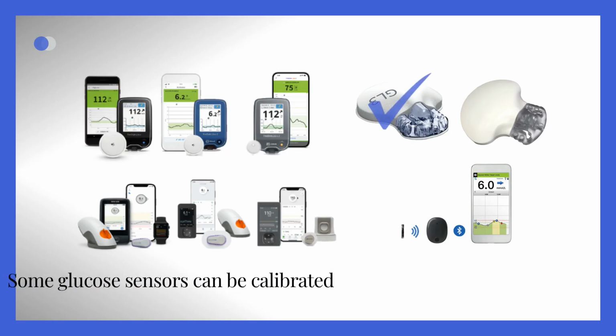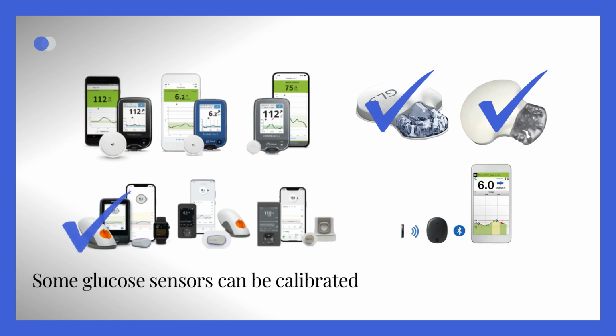In case your sensor continually demonstrates a divergence from finger prick readings under stable and target range glucose conditions, consider calibrating it if it supports this feature, or replacing it with a new sensor. When contacted, most companies will typically provide a replacement sensor free of charge.